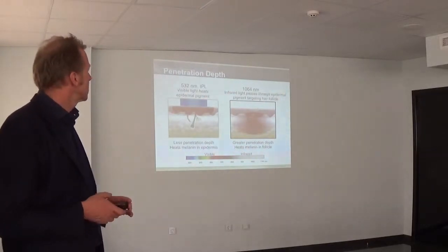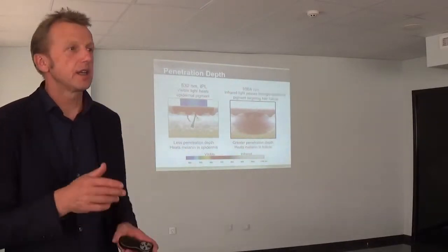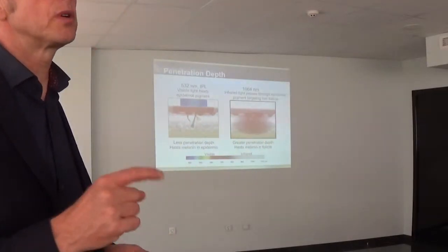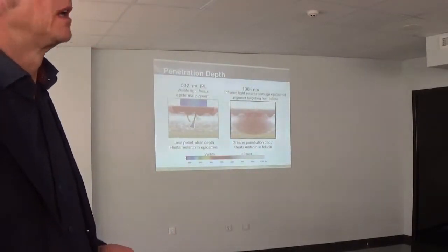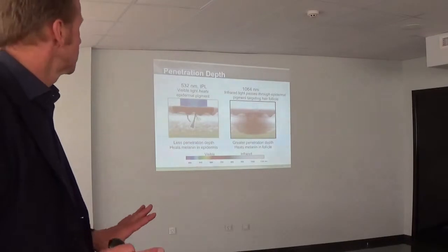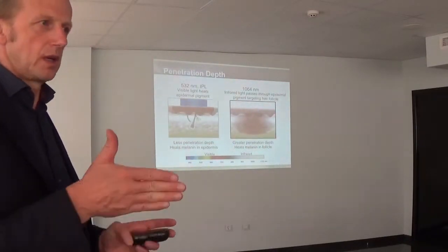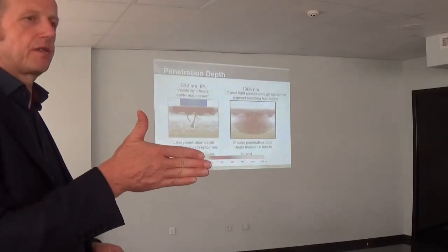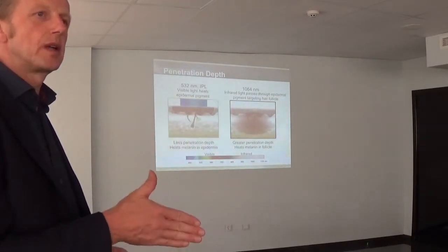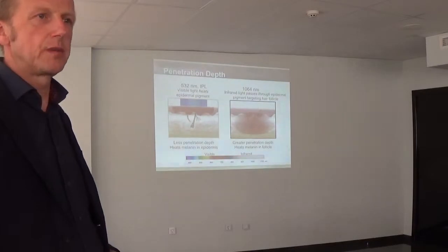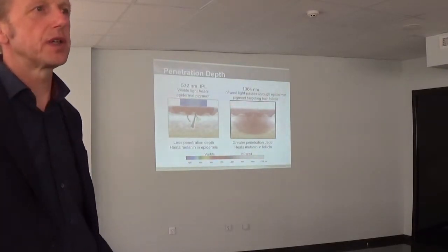In the XLV, we currently can increase the spot size by 0.1 millimeter even, but nobody's using it, so we are probably going to abandon that system. So it will be possible to have spot sizes from 3 millimeter to 12 millimeter with a 1 millimeter increase.